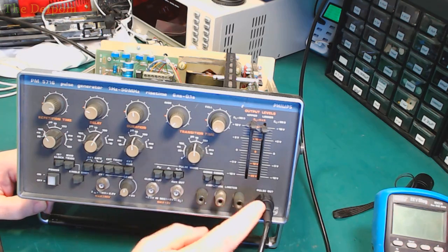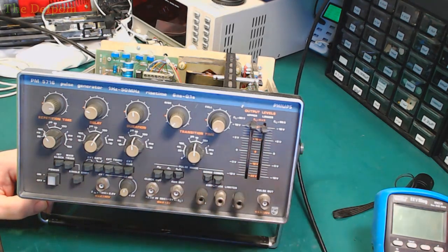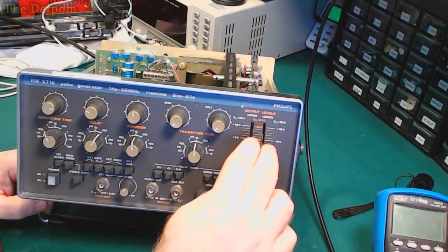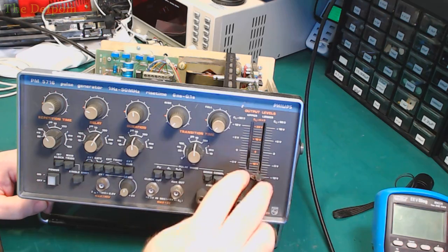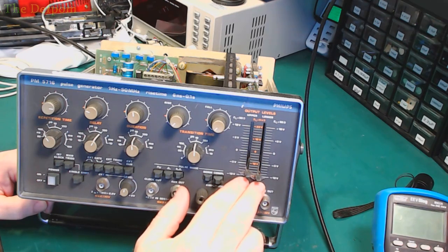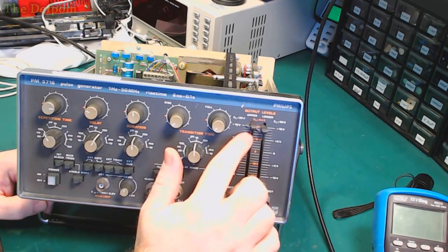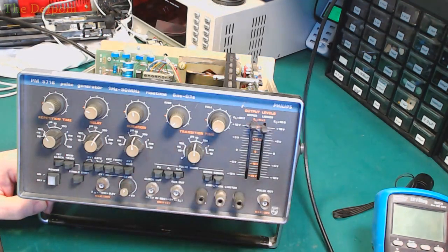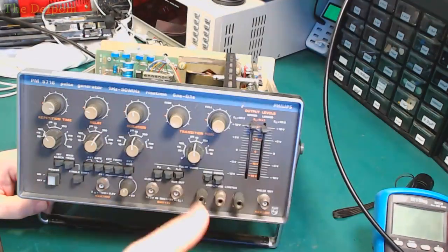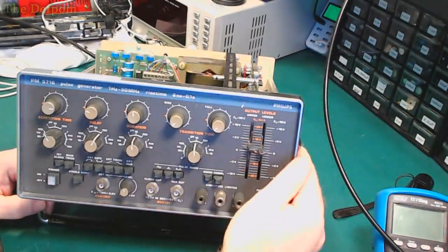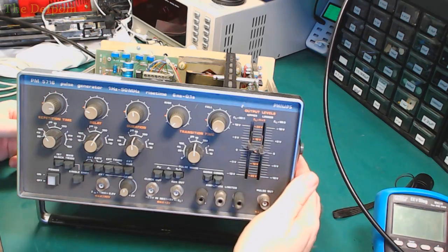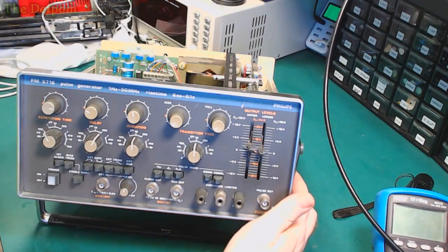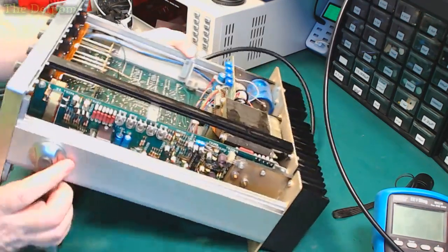But the pulse output doesn't have anything at all coming out, apart from a DC offset. If I add both slides together, it goes to minus 22.4 and positive 16.4. So there is a DC offset to the negative side. So there could be an input problem to the amplifier. Something's pulling it down. So that's where I'm sort of leaning towards now. So the output board there on the right hand side is what I need to look at next.